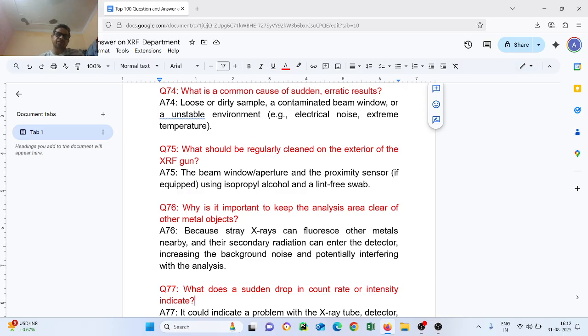Question number 76. Why is it important to keep the analysis area clear of other metal objects? Because the X-ray can cause fluorescence in other metal nearby, and their secondary radiation can enter the detector, increasing the background noise and potentially interfering with the result.